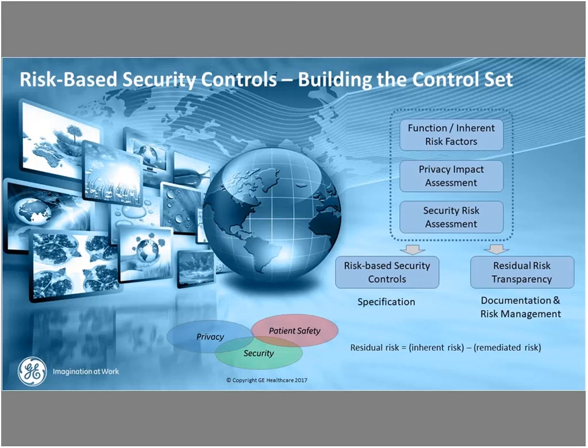And I did get a really good question here. Where do these controls come from? Well, I would strongly recommend security controls come from a well-accepted catalog of security controls. And at GE Healthcare, we have what we call the GE Healthcare Security Controls Catalog, but it is built predominantly on NIST 800-53. So we find that the NIST Security Controls Catalog, which is 800-53, is the best standard to use, and it's relatively easily mapped to virtually any security framework or security structure. But we've also added to it GE Healthcare defined controls, which are more specific to our medical devices. So our internal catalog is about 80% NIST, and we've added in a few of our own controls. So that was a great question.